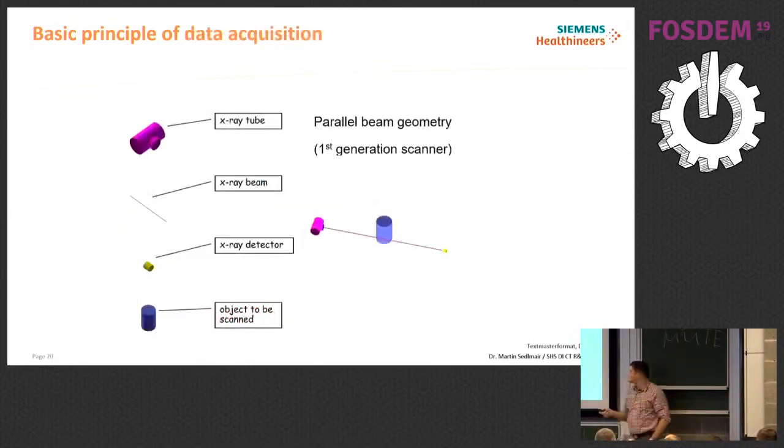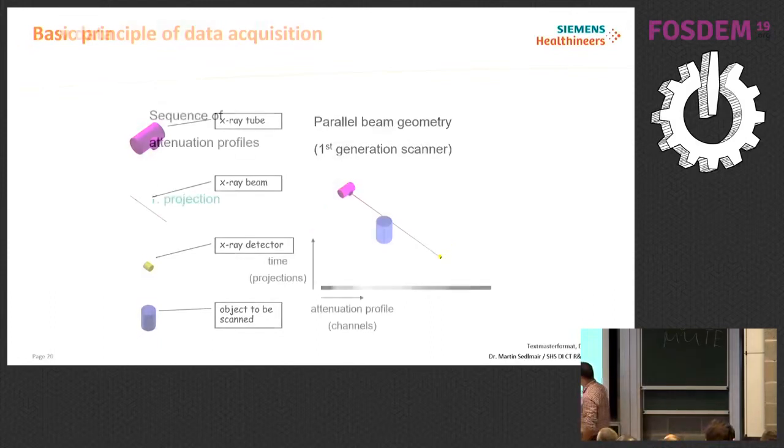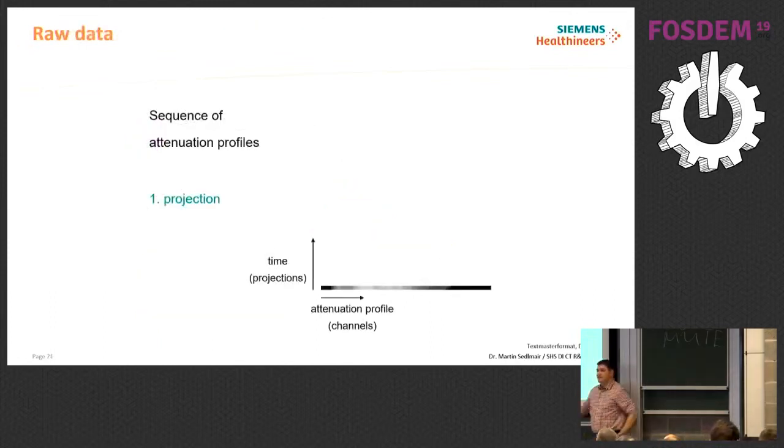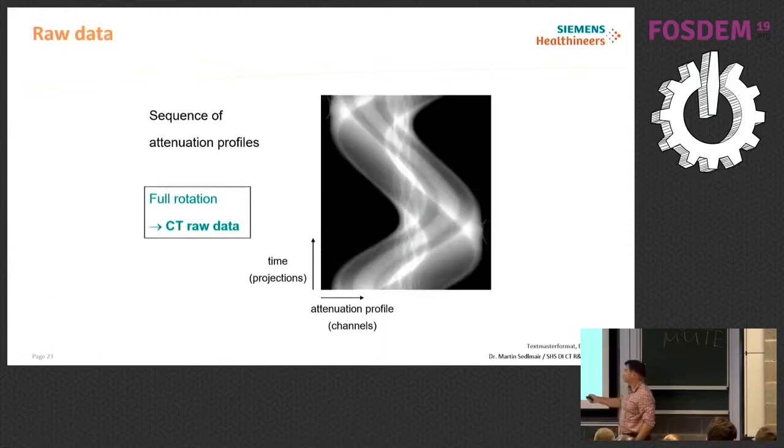And this is the so-called sinogram. Here you see the process, it's a little bit old animation, but in the end what you get is projections. There is a detector that has around 1,000 channels in one direction, and let's say 64 to 128 rows. So this is one projection from one angle. Then there is another projection. And if you finish this up, this is the so-called sinogram. In the end, it's a regular X-ray from many projections.